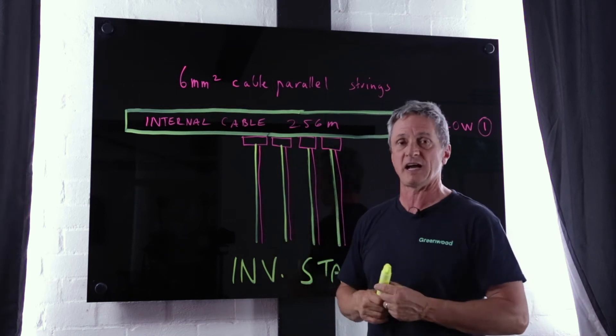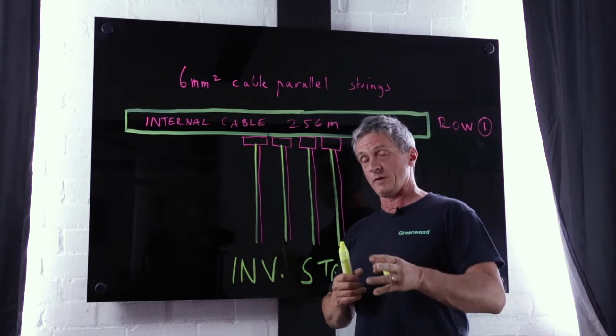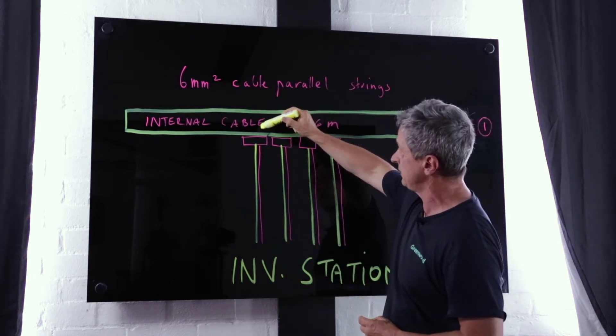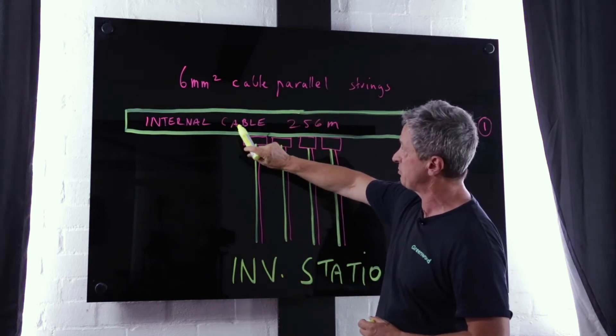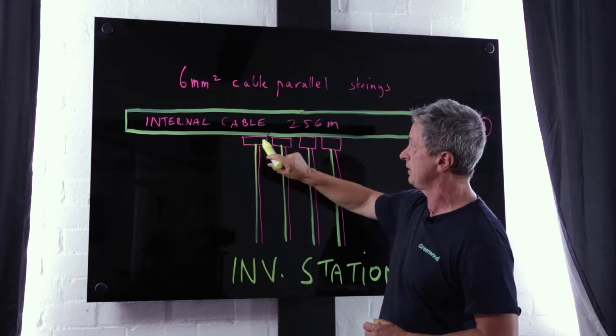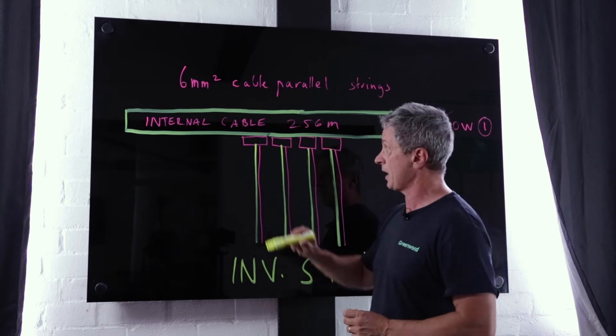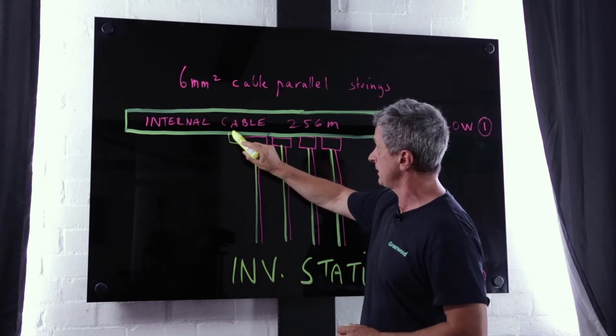We're going to still use 256 meters of cable. Whether we use 4mm or 6mm is another question. But at this point here we are effectively paralleling two strings into each of the four DC isolators. So we've got two strings coming in here, two strings in here, two strings in here and two strings in here.